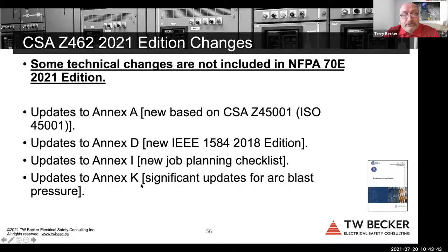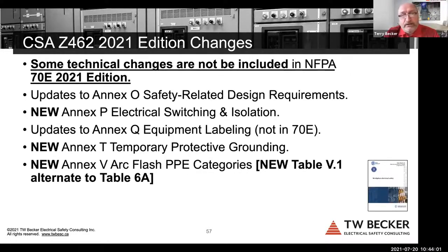The new job planning checklist was added. In Z462 Annex K, we actually adopted some new language around arc blast pressure that's not in the 70E 2021 edition. So this is another great thing that we did, because arc blast pressure has been miscommunicated for a decade, right? So we added language in to clarify that arc blast pressure is not dangerous. It's not high, right? It's not going to be high. There have been some papers presented and some additional information that the arc blast pressure is not what it was made out to be. And again, talk about that more offline.